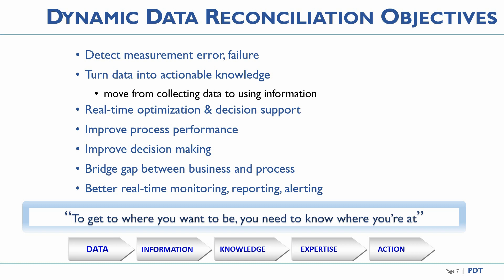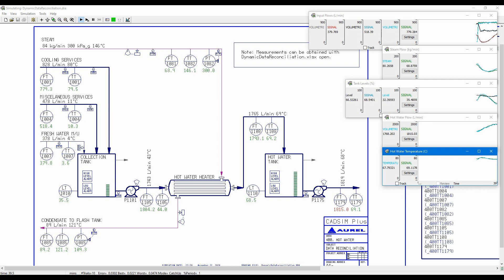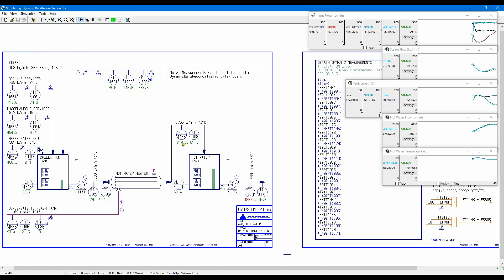I'm going to demonstrate this with an example where I will introduce some false measurement errors. This is an example of dynamic data reconciliation in action. Measurements are read in as shown on the sensors on this drawing. Data reconciliation tries many trials and ends up with a fit of the model to the entire measurement set. The green numbers on the charts are the measurements and the colored are the data reconciliation results. Now let's look at what would happen if we add some arbitrary error to two of these measurements — an error to the flow measurement of 200 and an error to the temperature of 20.